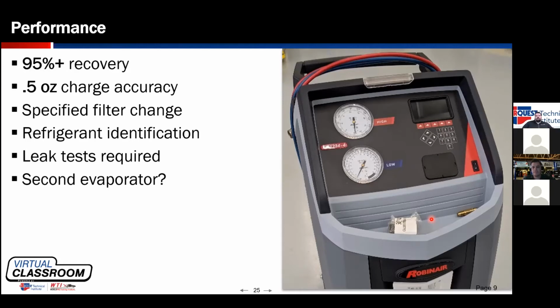There's two ways that the manufacturers can compensate for that. Either charge compensation, where the manufacturer says, we know that this machine and this set of hoses holds XY amount of refrigerant. So when we charge the system, we are going to add that much extra refrigerant to compensate for how much is left inside the machine. The other possible way to charge is using hose compensation, where after we finish charging the vehicle, we then close the high side service coupling, open the low side coupling, and allow all of the refrigerant that's in the high side hose and in the internal plumbing in the machine to be pulled into the vehicle through the low side.